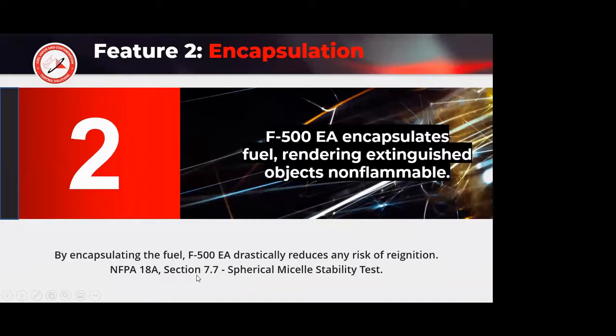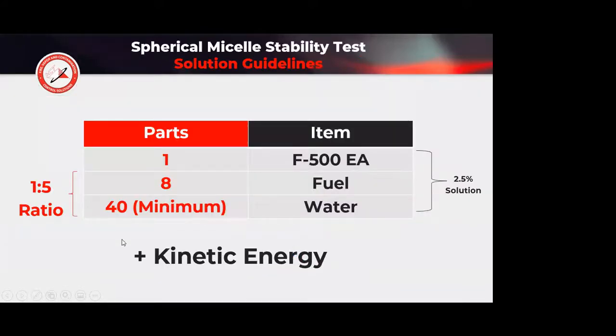We already talked about section 7.7. If we go into 7.7, it says you use a certain amount of agent, a certain amount of fuel, and add a certain amount of water. In the NFPA standard, this is left to the discretion of the manufacturer—they didn't want to tie it to just one product like F500, since another product might require a different mixture. Our mixture for the F500 encapsulator agent is 1 part F500, 8 parts fuel, with 40 parts water, mixed together. Now I'm going to show a video of the actual NFPA 18A section 7.7 protocol.